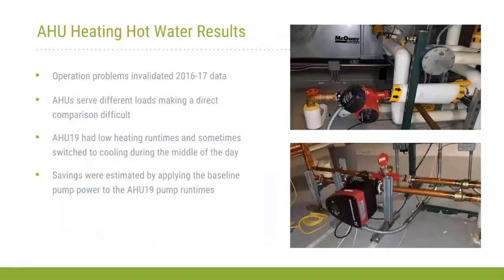Okay, next slide. So the air handling unit demonstration was a little more complicated than the other one. When we first selected these, both air handlers were operating for about 20 hours per day. But the air handling unit 19 was not meeting discharge air temperature set point, and it was not responding to the control mode signals correctly. And it was determined that the facility needed to be retro-commissioned, and so they did a full retro-commissioning of the entire facility, which delayed the demo by about a year. And then after the facility was commissioned, the air handling unit number 19 was only operating very intermittently.